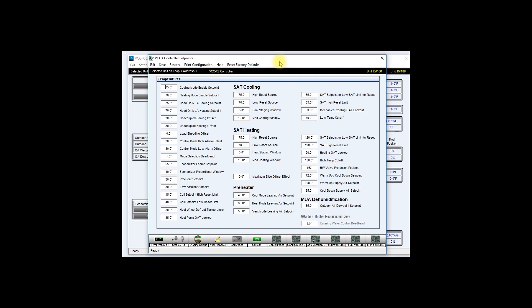Please note that you can only save and restore setpoints and configurations from and to the same style of controllers. If you try to load setpoints from a VCCX to a VCCX2 for instance, Prism 2 will show you an error message preventing you from making this mistake.